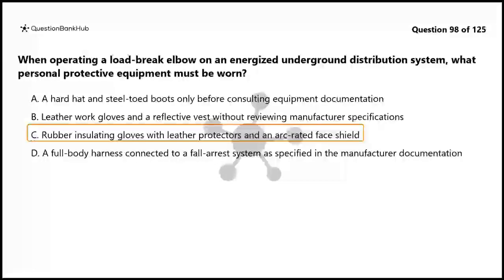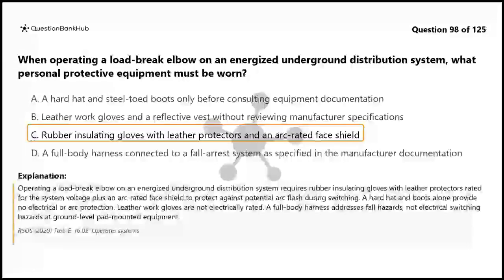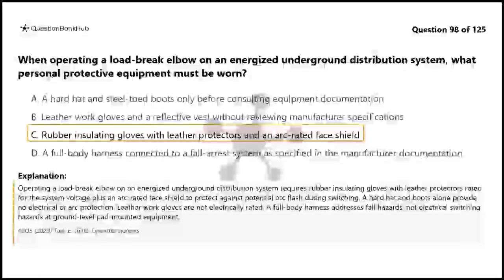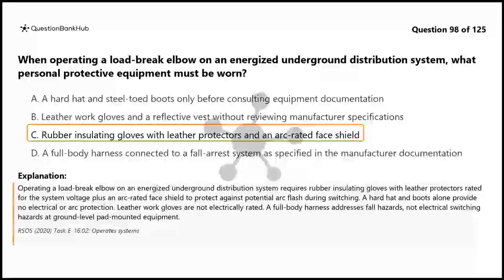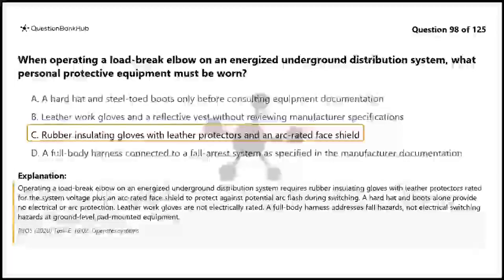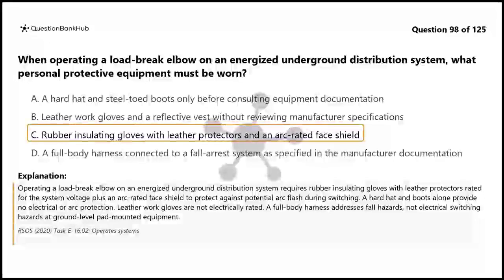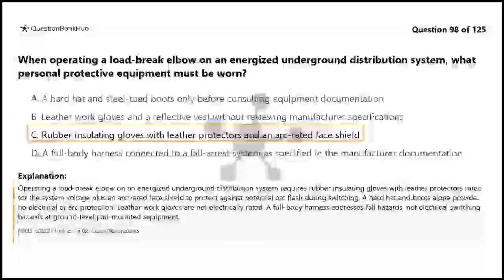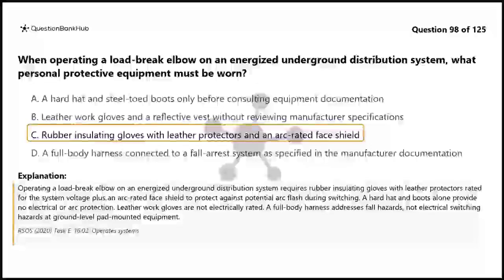The correct answer is C. Operating a load-break elbow on an energized underground distribution system requires rubber insulating gloves with leather protectors rated for the system voltage plus an arc-rated face shield to protect against potential arc flash during switching. A hard hat and boots alone provide no electrical or arc protection. Leather work gloves are not electrically rated. A full body harness addresses fall hazards, not electrical switching hazards at ground-level pad-mounted equipment.